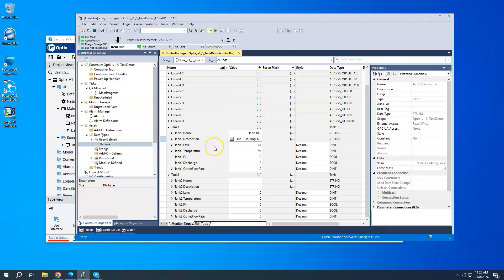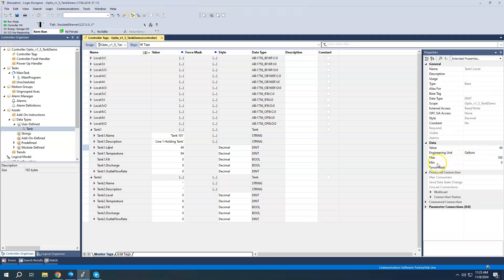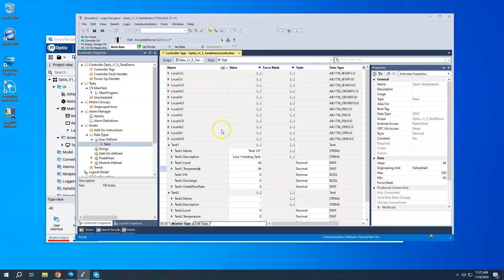Just to kind of show under like level, I'll go ahead and blow this up. So if I click on the tank 1 level and over here in the properties, I've enabled the extended properties. And I basically put in an engineering unit for gallons and min and max values. Just say it's a 100 gallon tank, so from 0 to 100. Did the exact same thing on the temperature. I have the engineering units enabled and the min and max. So I went with Fahrenheit and I kind of just took an RTD range, say from minus 30 to 250 degrees Fahrenheit as the min and max range. And that's pretty much all I've done here as far as setting up the tags.